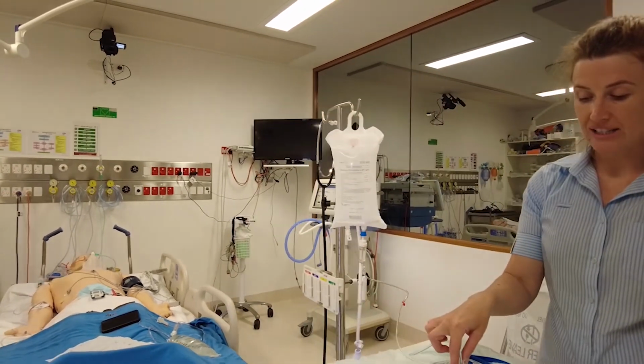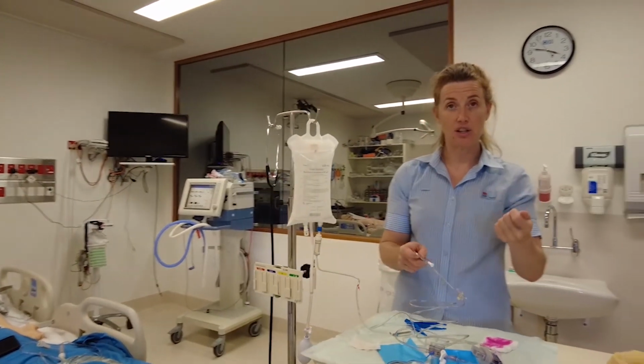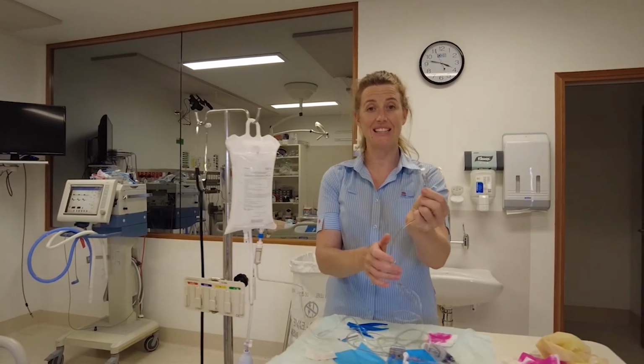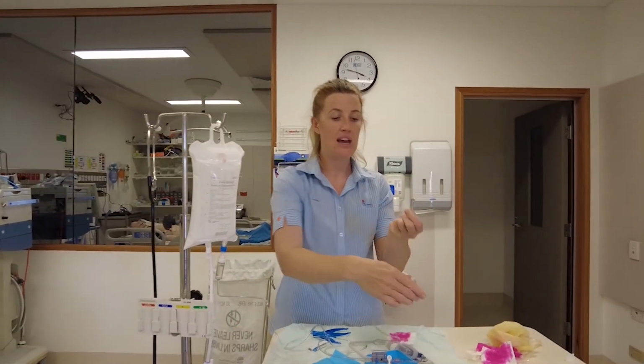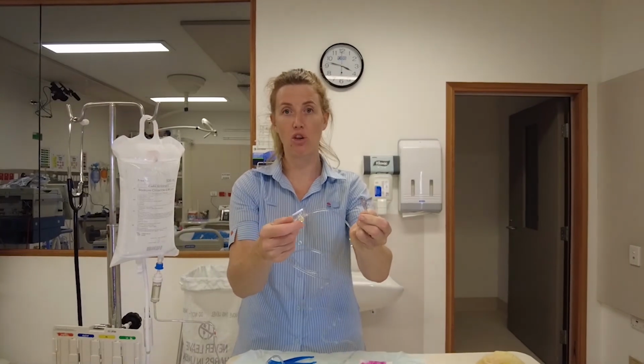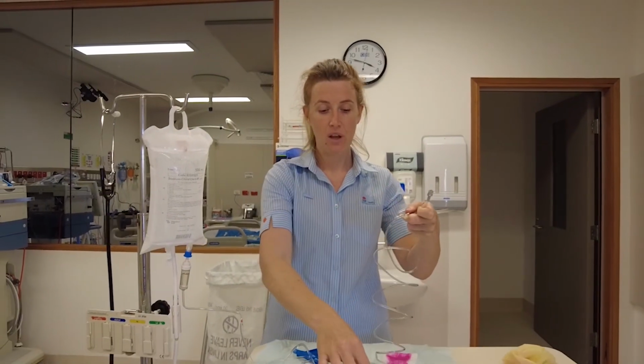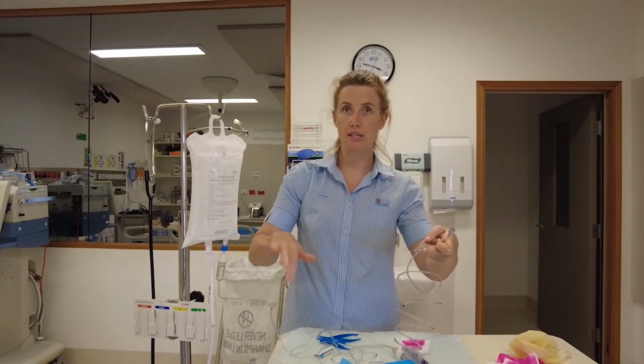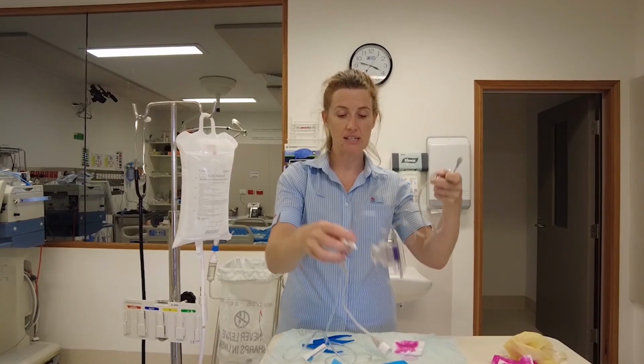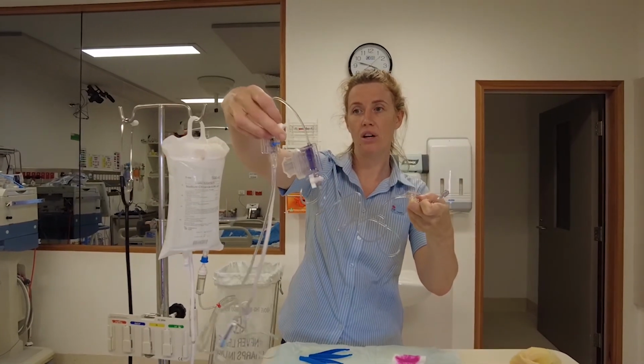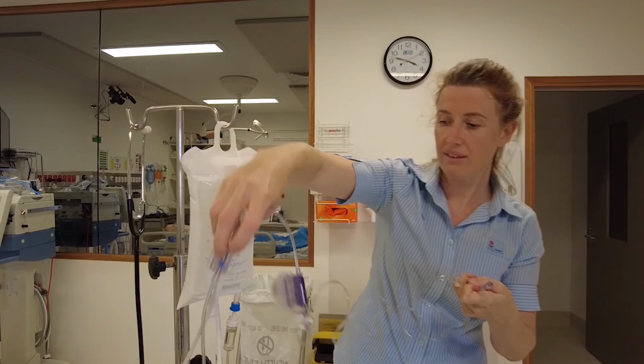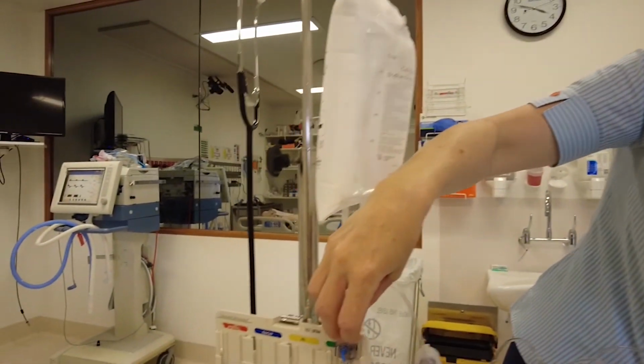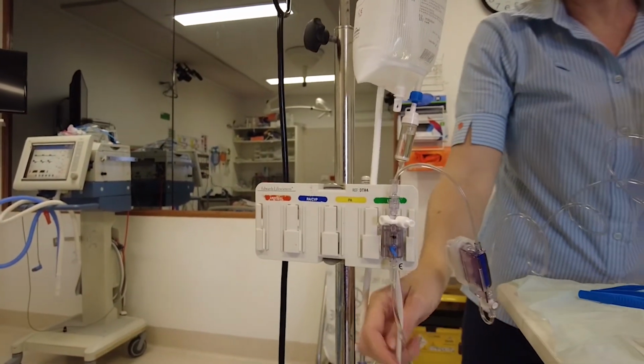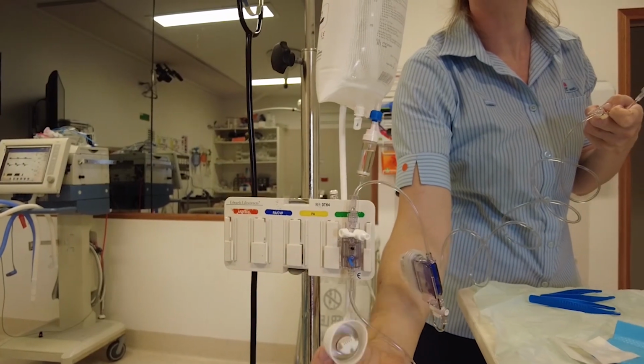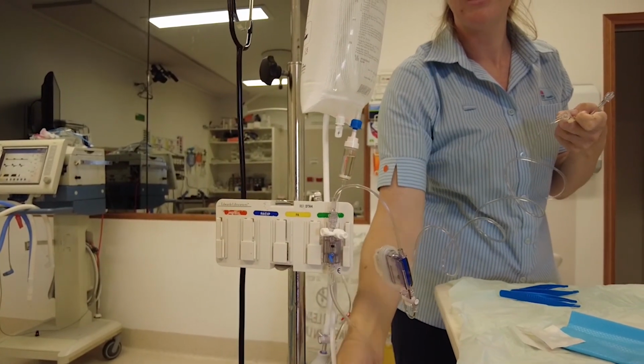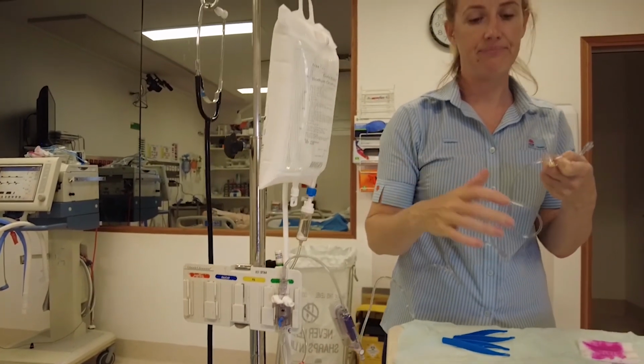Once the medical officer has inserted the arterial line to the patient, they're going to connect to this end. So they're going to take that cap off, connect that to the patient, secure it, and apply a dressing. Because now we've got a closed circuit to the patient, we can come and touch this. We're going to pop our transducer in the holder. We're going to attach our arterial pressure cable to our GE monitor, and we're going to zero the line.